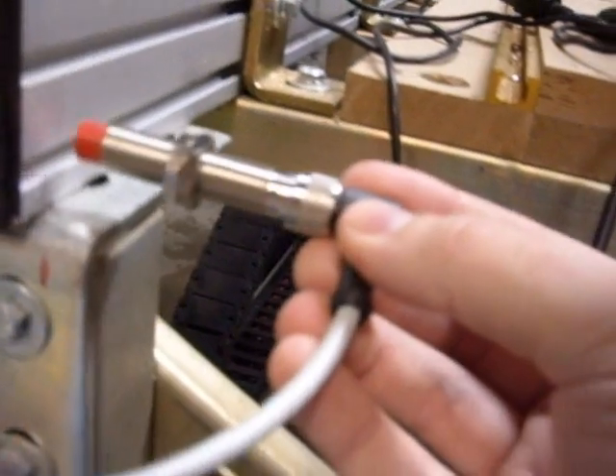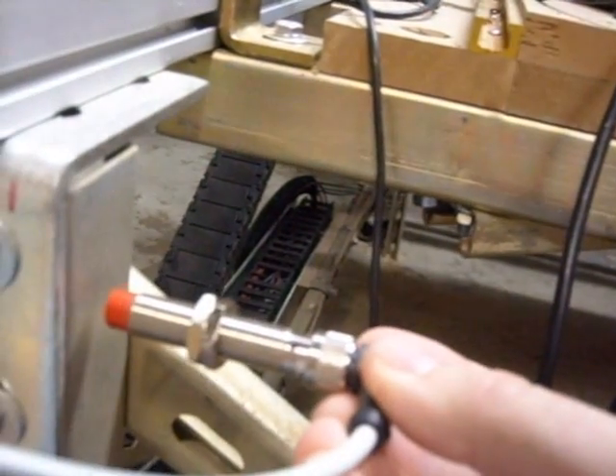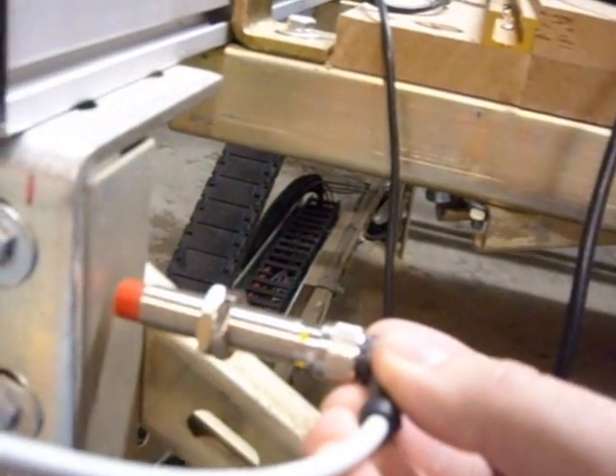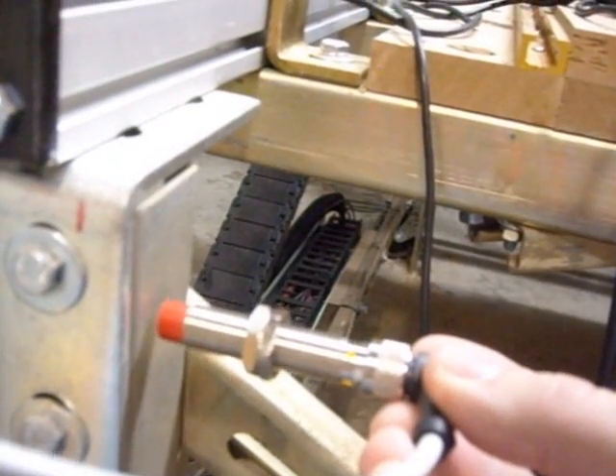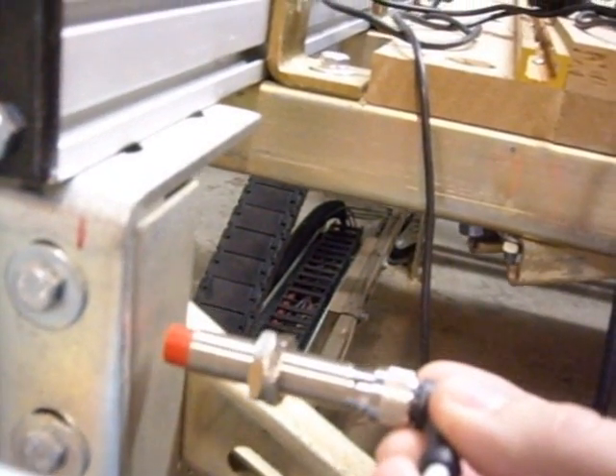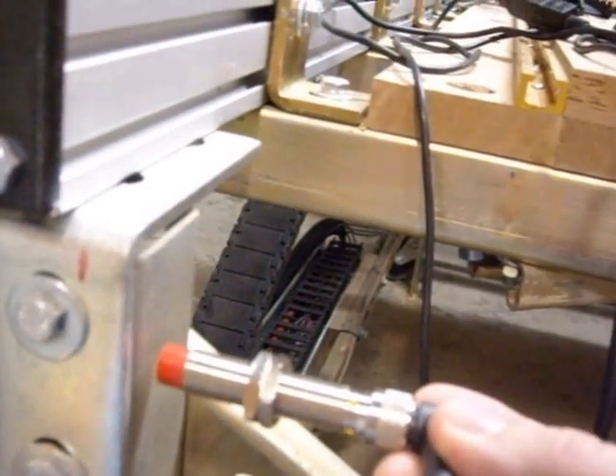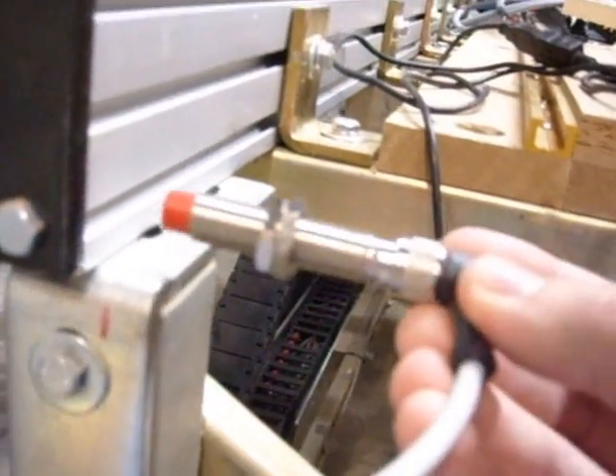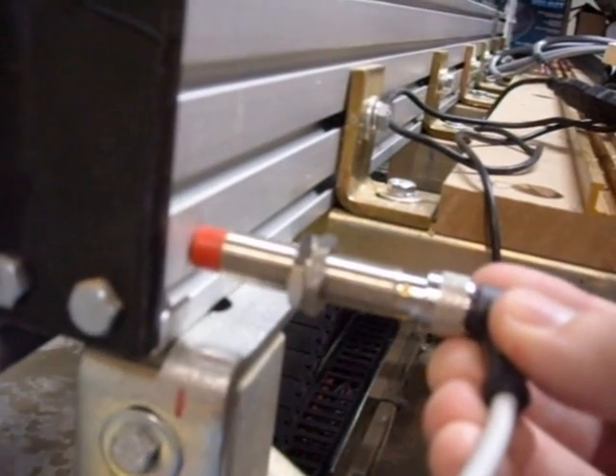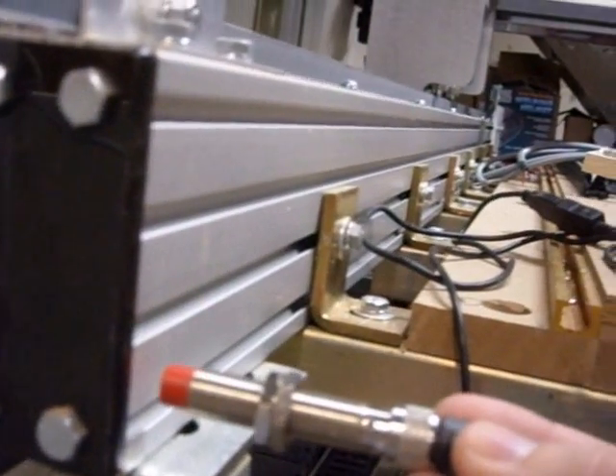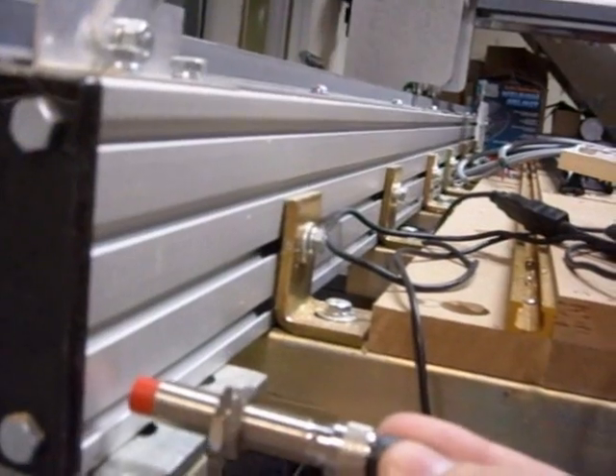For example, if I go to the galvanized steel here, it'll start lighting up probably between four, no more than three millimeters away. The aluminum might barely, probably got like a mil or two off of it to get the thing to light up or to make that contact closure.